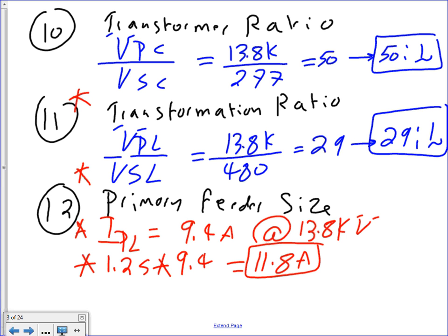The third thing is, you're going to take the 11.8 amps. Now we're going to take this to the table. This table, I think we used it last time too. 310.60. Let's go to 310.60.